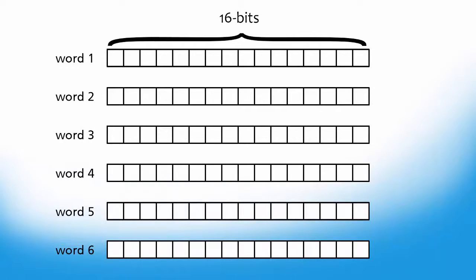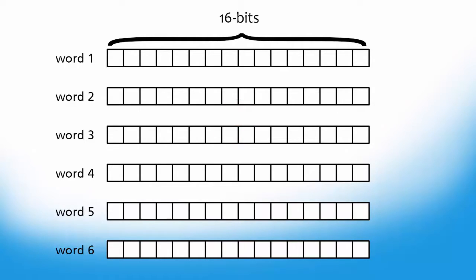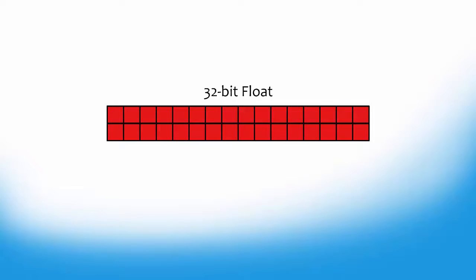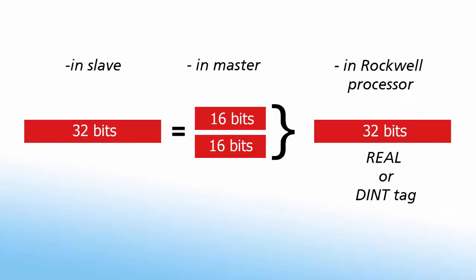This presents a small complication since the internal memory of ProSoft modules are comprised of 16-bit word addresses. The solution is to break the 32-bit value into two separate 16-bit registers and then recombine them back into a 32-bit real value. This is accomplished by copying the two 16-bit registers to one real tag in the Rockwell processor.